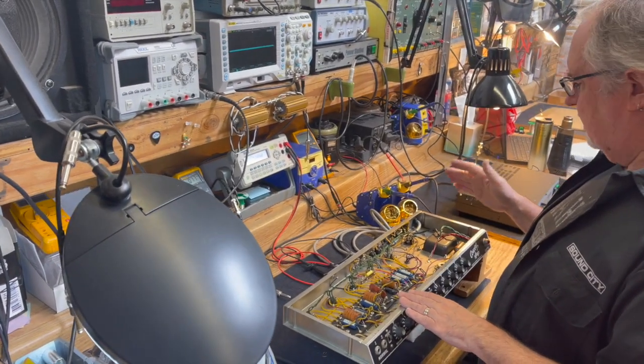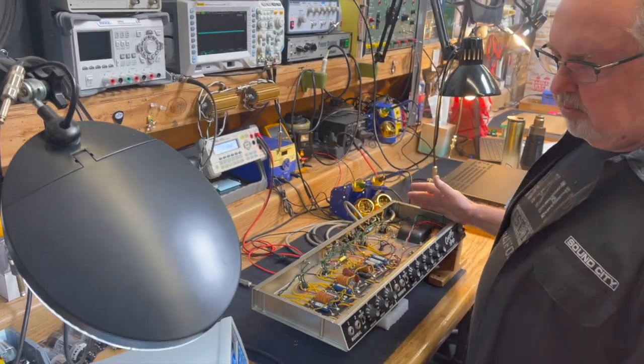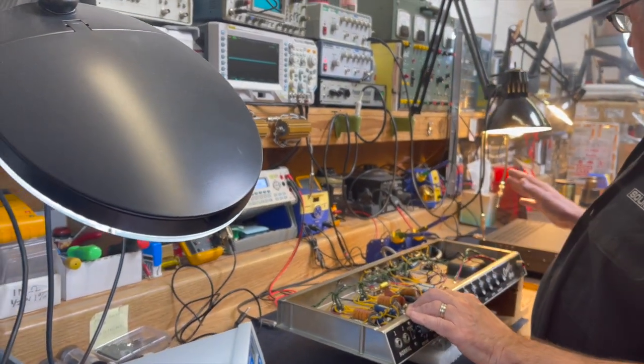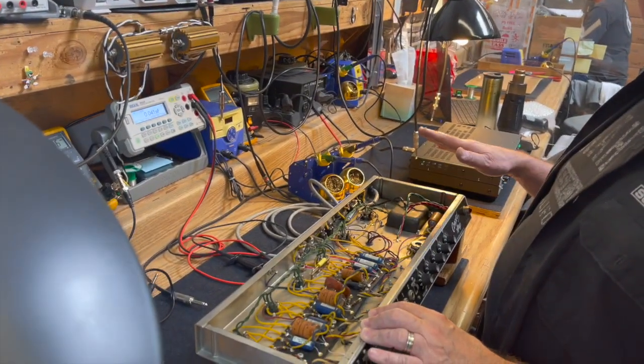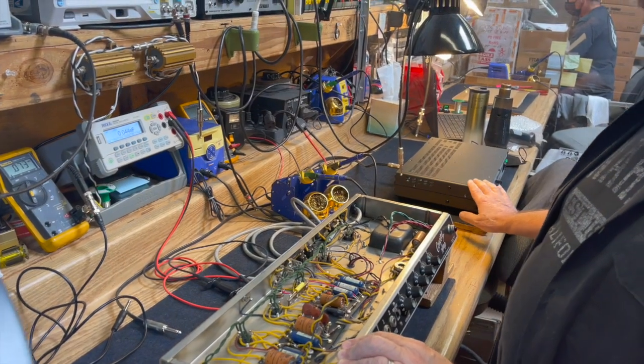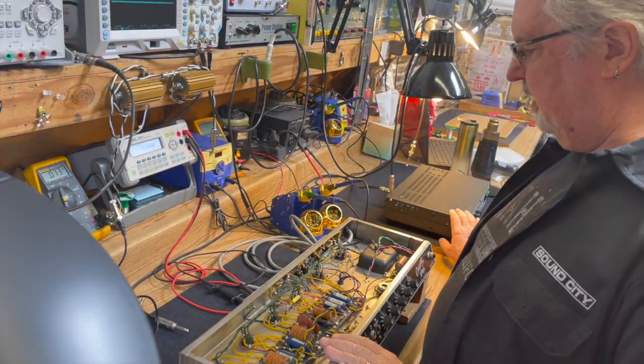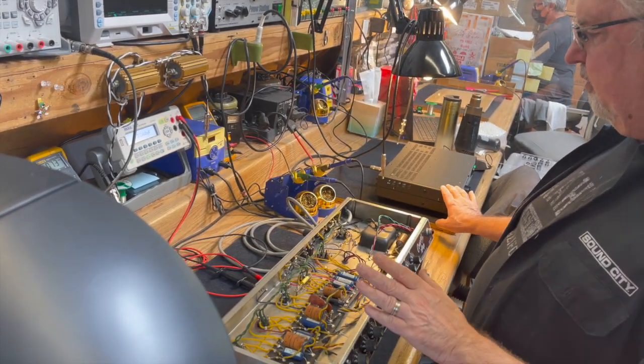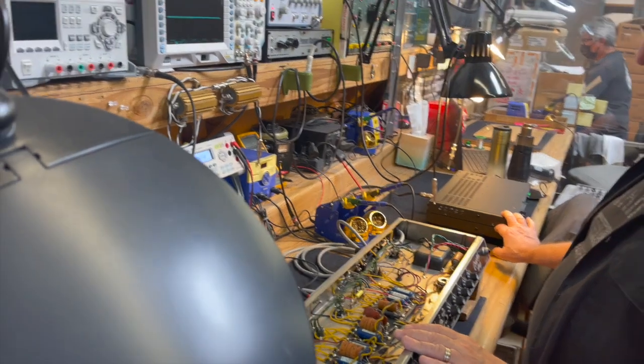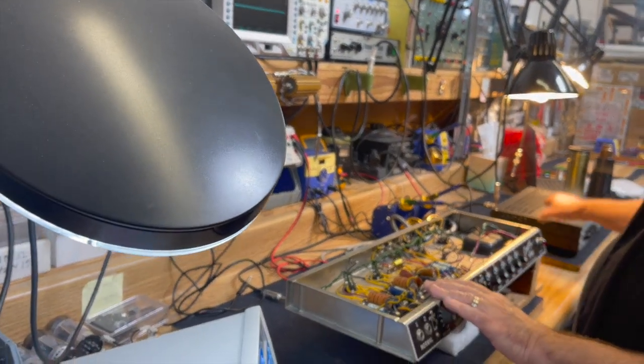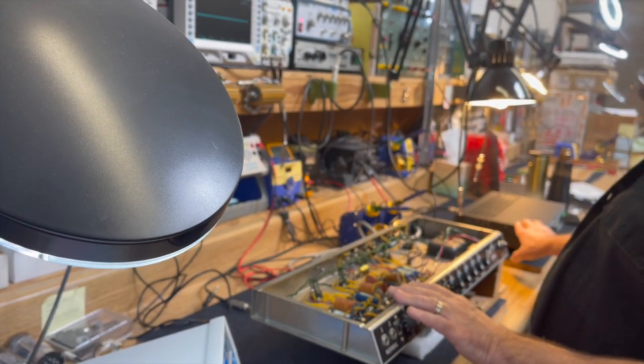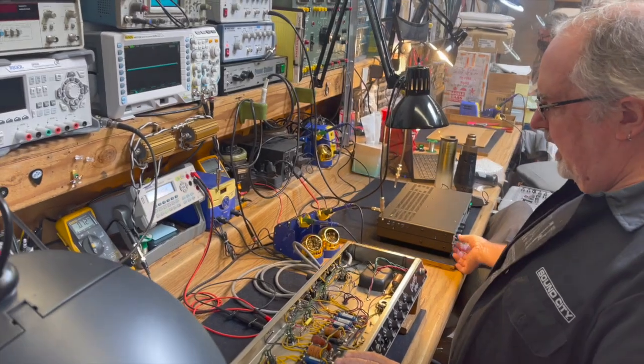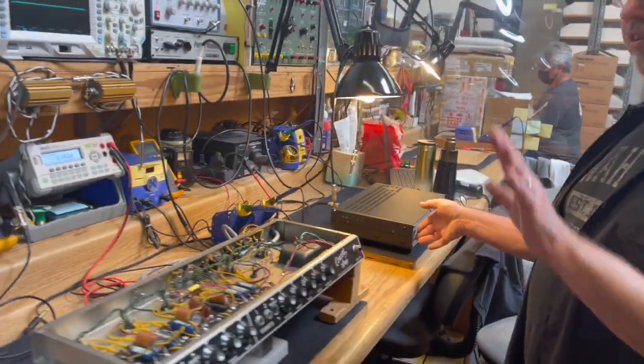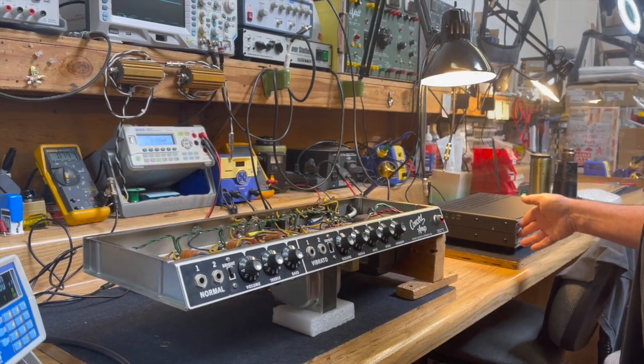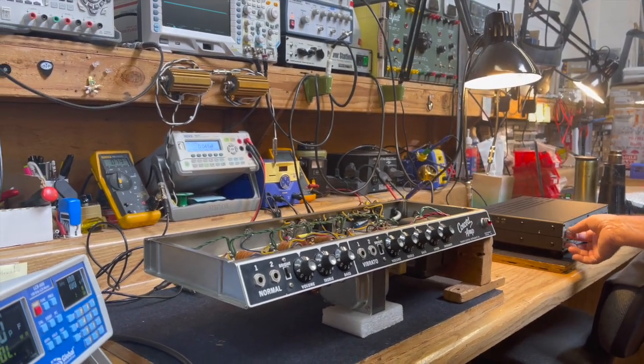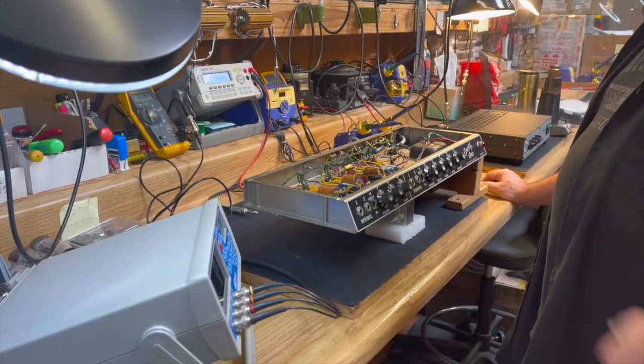In this case we're trying to extract a bunch of different data, so I'm using the power station as the load for a couple reasons. One, it can switch to 4 ohms, which is the impedance of the concert amp going into four 8-ohm 10s, so it's 2 ohms — and this also has a 2 ohm setting. Swiss Army knife, I tell you. It's also got reactive load switches, so when we're checking it and want to see that it behaves like an amp plugged into a speaker, we can set it into reactive mode and get that behavior. Wonderful — so we can observe all that.